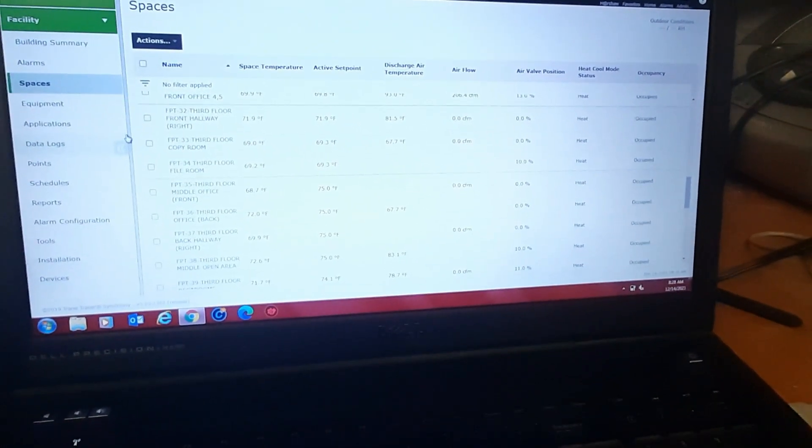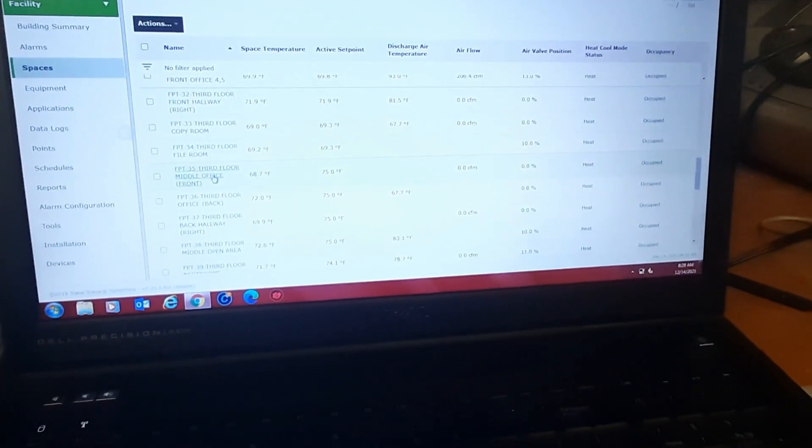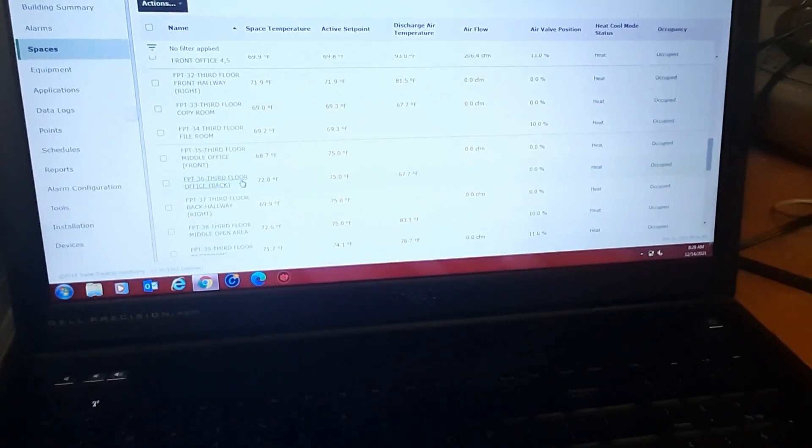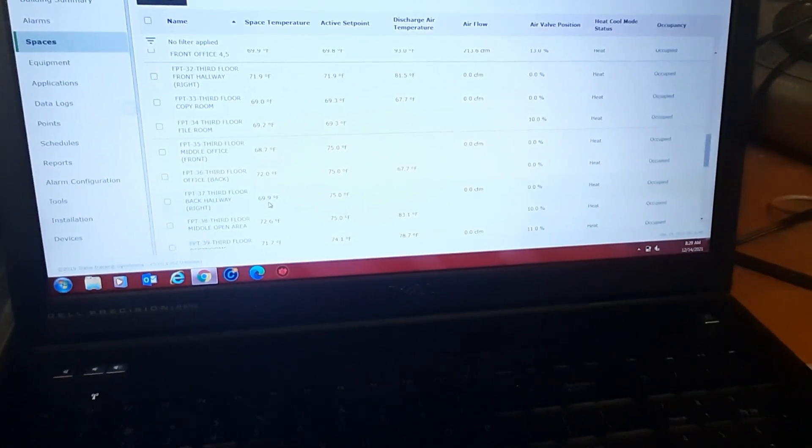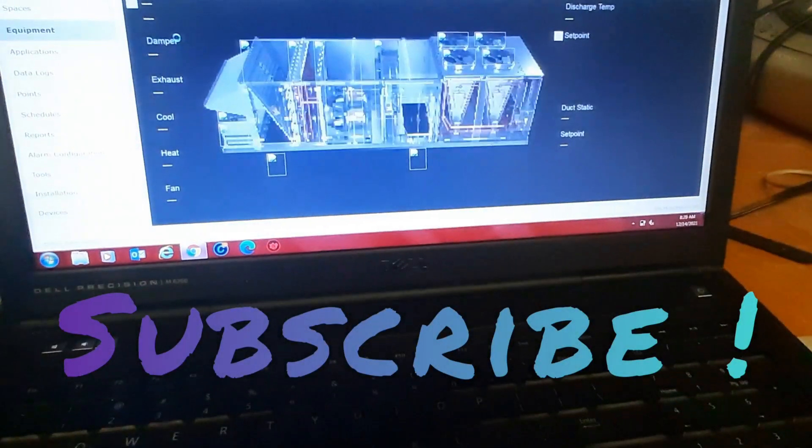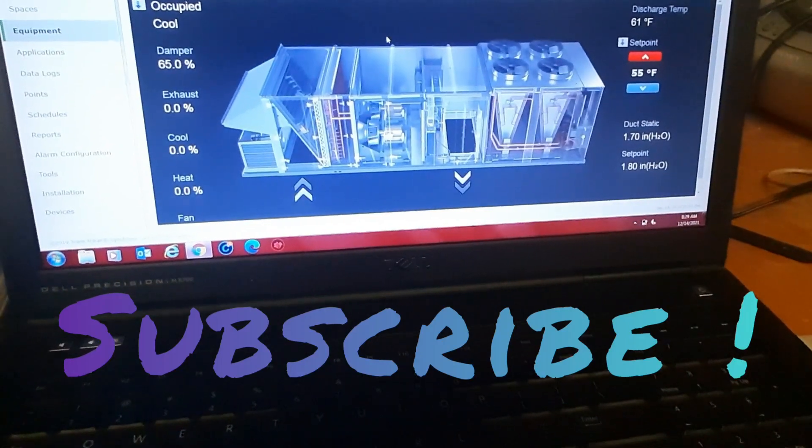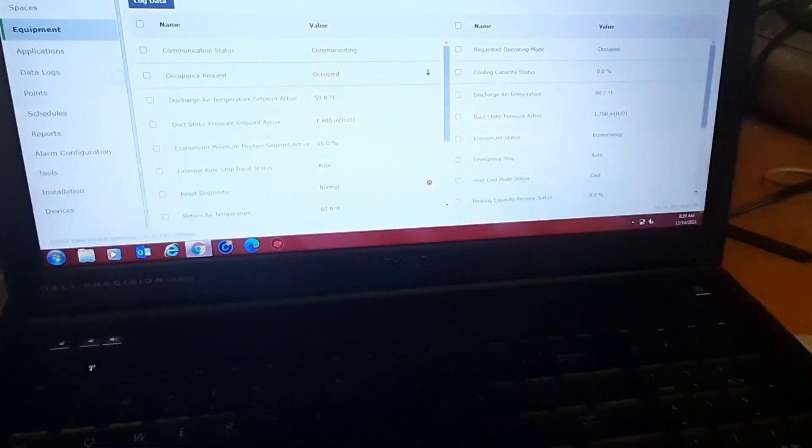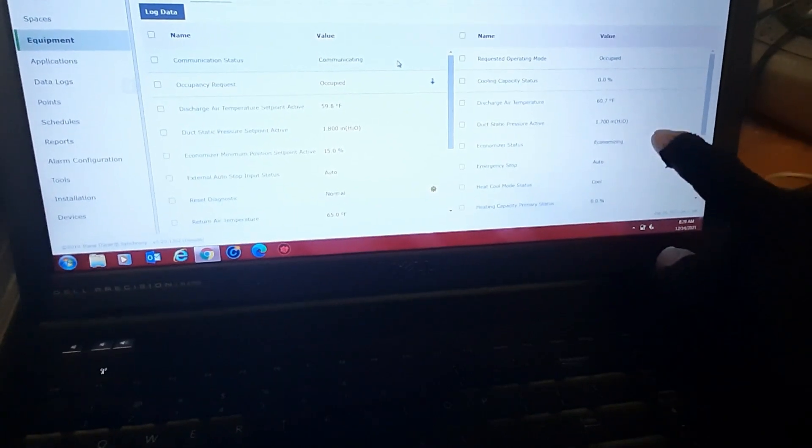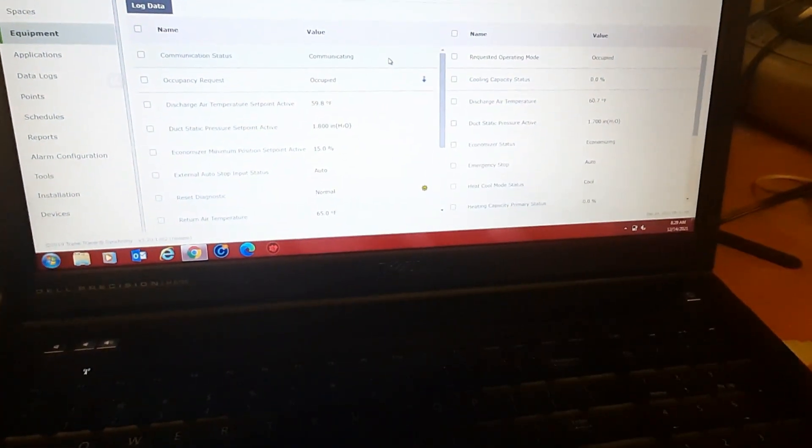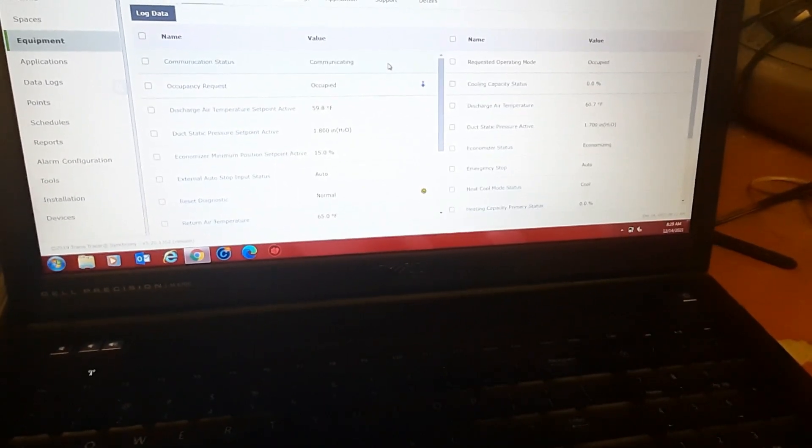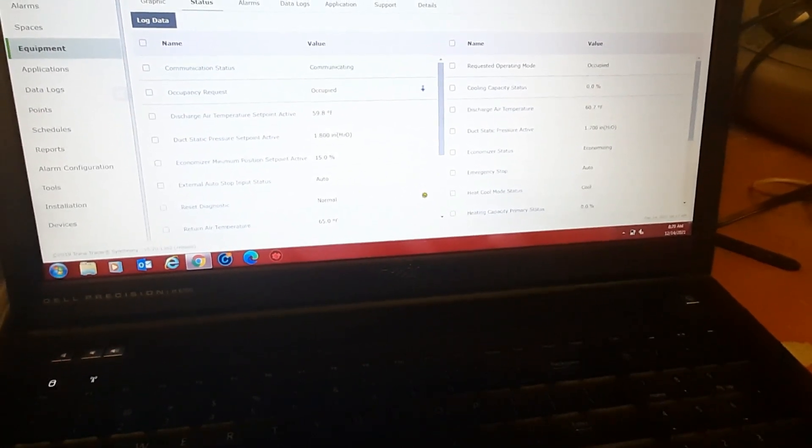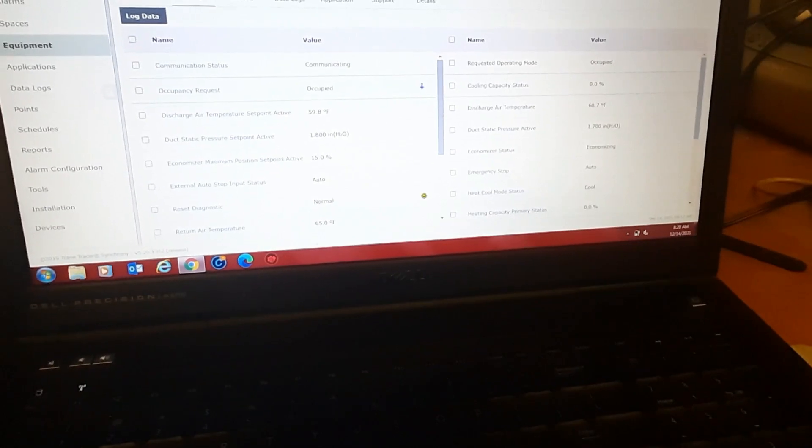So that's some VAV boxes, no heat call for these two boxes here, 36, 37. So the biggest thing to start with is just knowing how our building works. We've got an IntelliPak and we maintain 55 degree supply air. Right now you can see my discharge temperature is 60, my set point active is 59.8, so we're right around that. There is a 10 degree reset, so maintain 55 as the temperature outside goes down, my discharge air temperature will actually go up to help keep heating space.